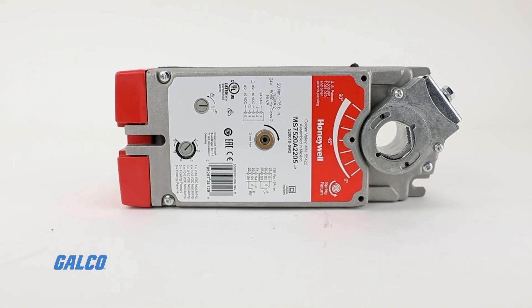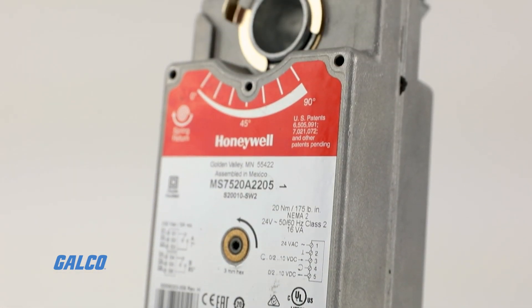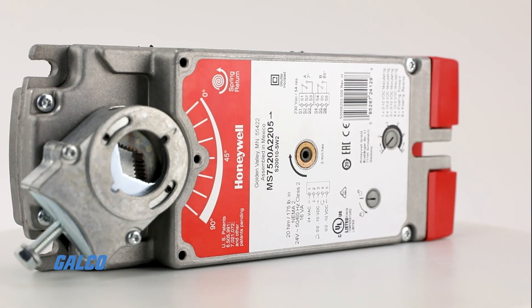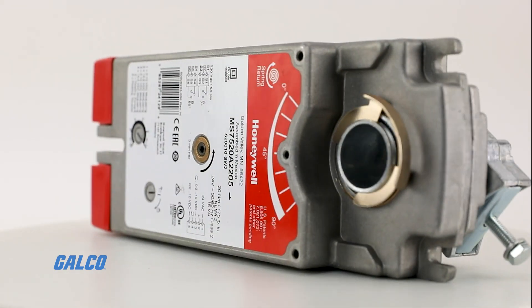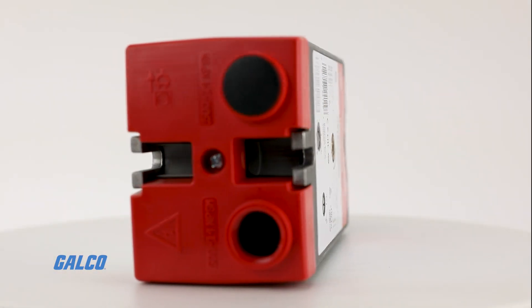Available in MS4120, MS7520, and MS8120 models, this spring return direct coupled actuator has a 175 pound-inch torque rating and is housed in aluminum.